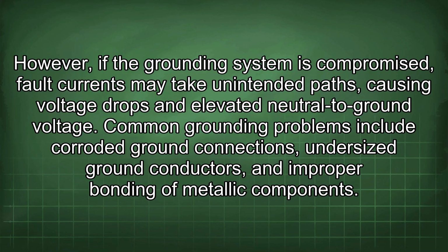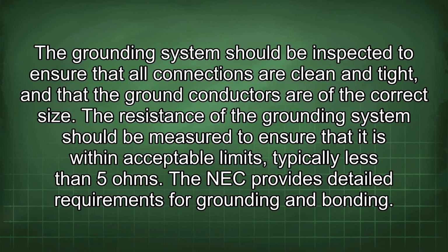However, if the grounding system is compromised, fault currents may take unintended paths, causing voltage drops and elevated neutral to ground voltage. Common grounding problems include corroded ground connections, undersized ground conductors, and improper bonding of metallic components. The grounding system should be inspected to ensure that all connections are clean and tight, and that the ground conductors are of the correct size. The resistance of the grounding system should be measured to ensure that it is within acceptable limits, typically less than 5 ohms. The NEC provides detailed requirements for grounding and bonding.